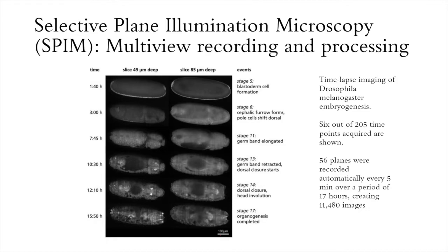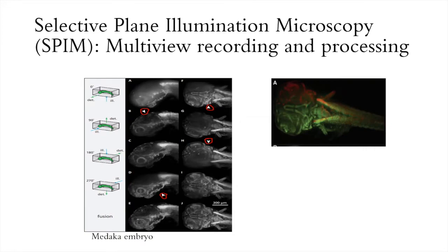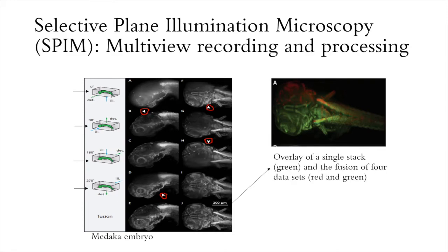For this figure, the images were orientated so that the illumination occurs from below. This results in a slight drop in intensity and clarity from the bottom to the top of each slice. Nevertheless, the information content across the embryo is nearly uniform and we can clearly see the development of the embryo. However, in the imaging of the live medaka as shown here, a stack is recorded for each orientation at 0, 90, 180, and 270 degrees. The stacks were then re-orientated in the computer to align them with the stack recorded at 0 degrees. The red circled arrowheads show the well-resolved parts, which are close to the detection lens and facing the illumination plane. The fusion of these four data stacks yields a superior representation featuring similar clarity and resolution throughout the entire specimen, as the image combination procedure inherently favours well-resolved and bright features over poorly resolved and less visible ones.